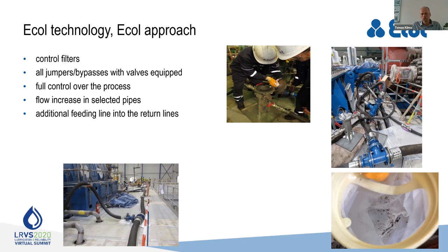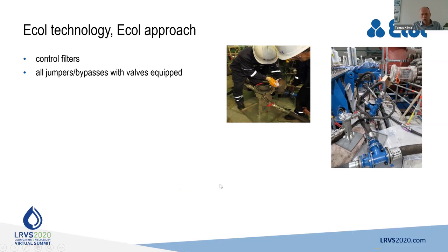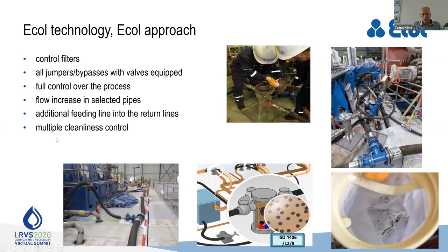Usually the return lines have a much higher diameter than the discharge to the lubricated component. So you need to flush these returns also with high velocities, which is allowing you, when you build such a line to that point, to do it. An additional feeding line is visible here, as well as a lot of bypasses. The specific control filter I told you about, this is the mesh where we control the particles, and multiple cleanliness control on that.